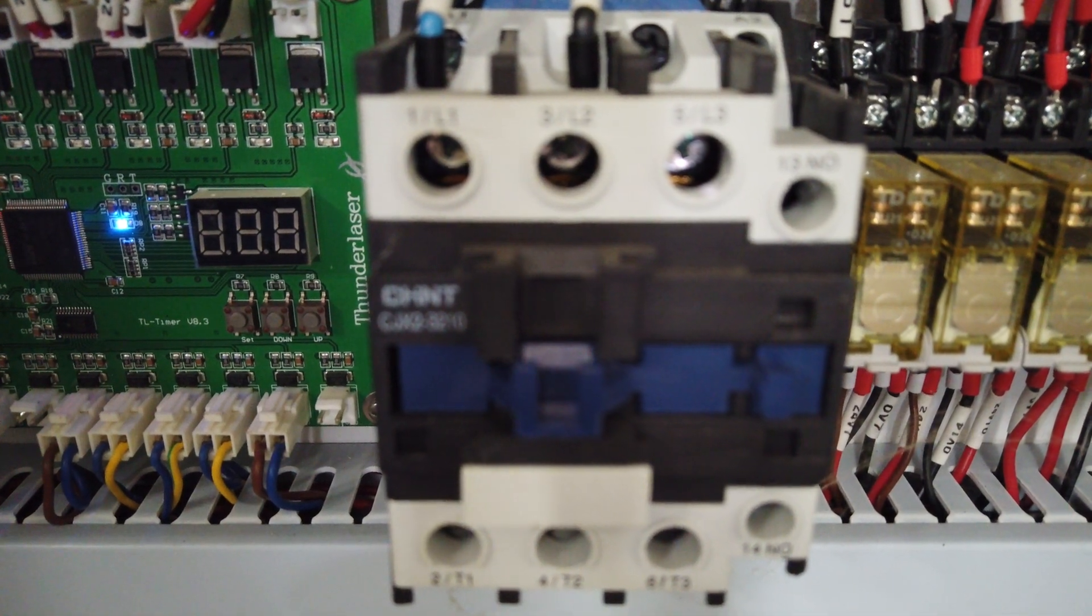Now if you're not getting that, you need to check the laser power switch, check the connections in here behind it, and also make sure that all the screw terminations are tight on the contactor that you can see.